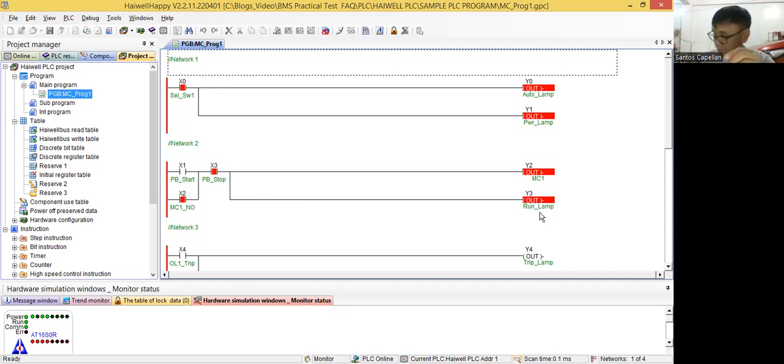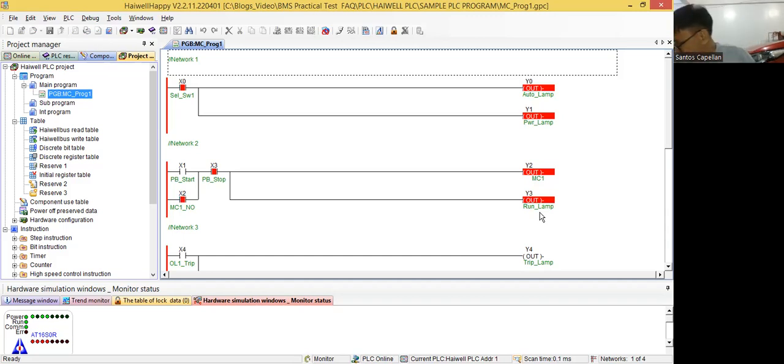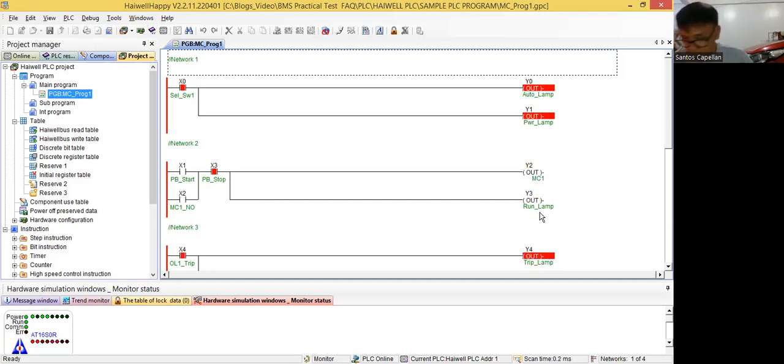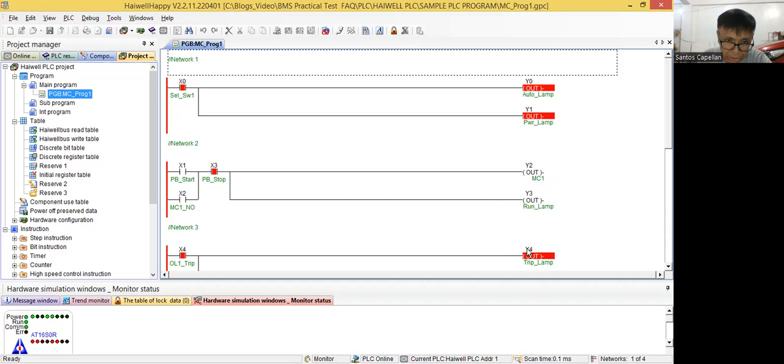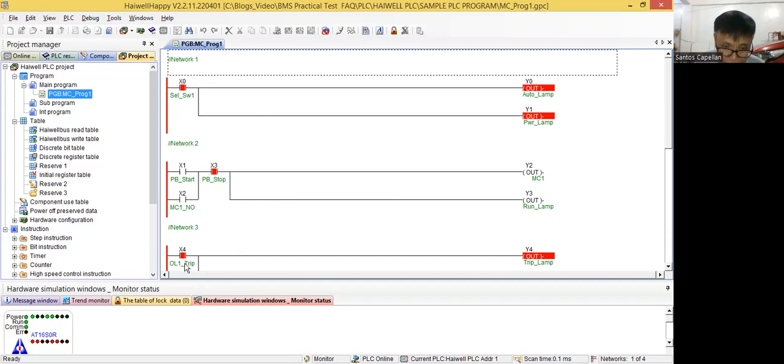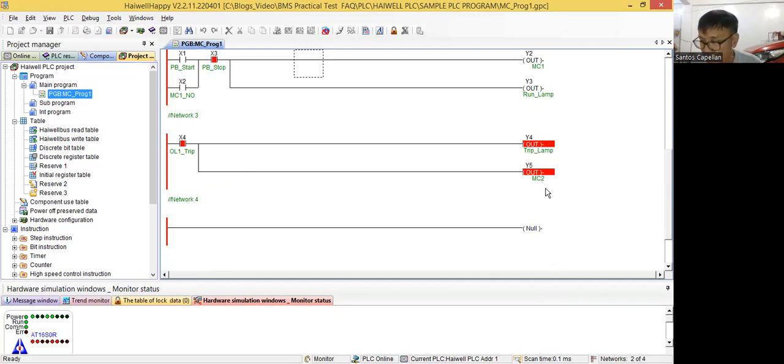Now my motor control, my magnetic contactor is energized. Then my run lamp is also energized. Now I will try to trip it so that we can see if it will try to run the standby. I will trip. Hold on. So as you can see, the MC one run lamp gone, then the overload protection normally open contact closes, then it will run the trip lamp. Then at the same time. Where is that one? Then this is the branch output turning on my simple relay or my relay to activate the standby fan.